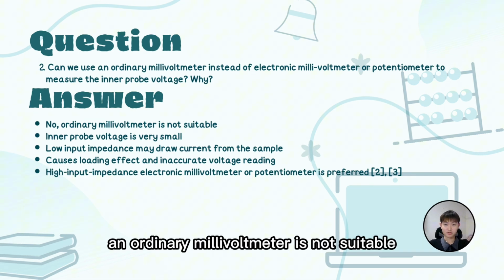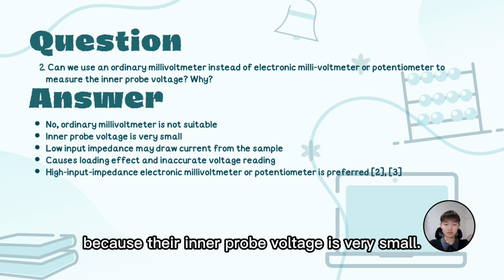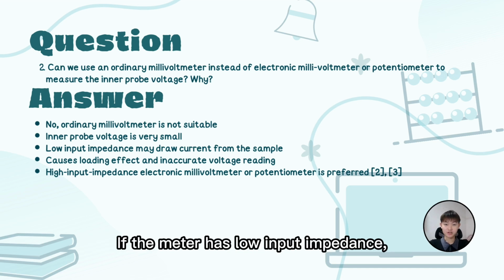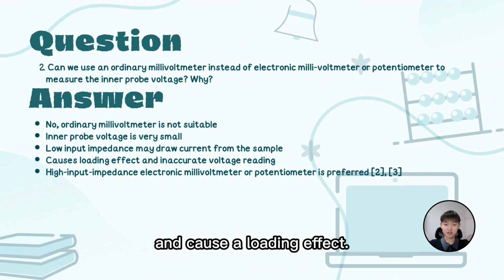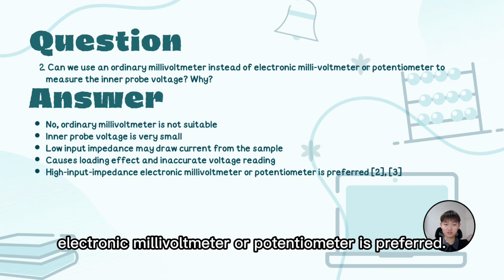For question 2, an ordinary millivoltmeter is not suitable because the inner probe voltage is very small. If the meter has low input impedance, it may draw current from the sample and cause a loading effect. Therefore, a high input impedance electronic millivoltmeter or potentiometer is preferred.